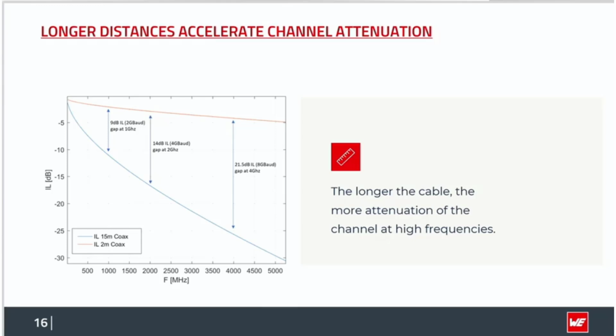When having a look at the insertion loss in this graph, you can see the comparison between a 2 meter coax cable and a 15 meter coax cable. For a data transmission working at 1 gigahertz Nyquist frequency, we have a gap of 9 dB, meaning 9 dB higher damping. And when going to 4 gigahertz transmission, for example, we have close to 22 dB. So this means the higher the frequency gets, and the longer the cable gets, it is getting more and more challenging to get the system working.